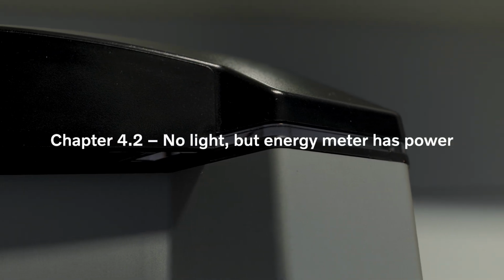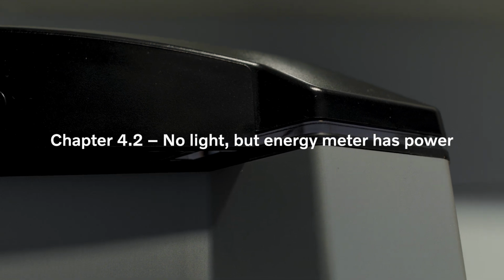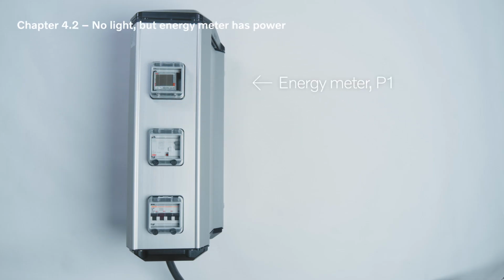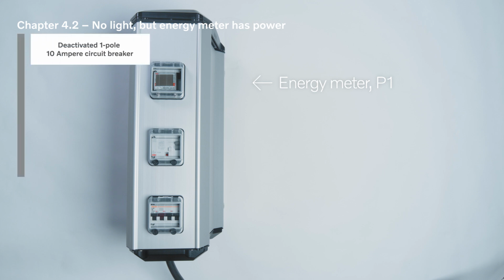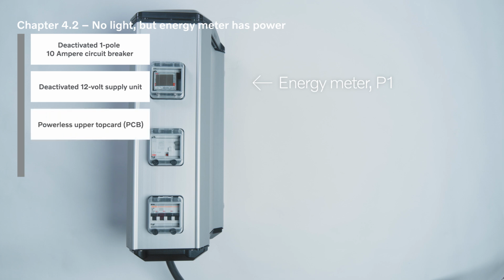If the LED indicator isn't displaying any light, but the left side energy meter, P1, has power, the power failure may be caused by one of the following issues: a deactivated 1-pole 10 ampere circuit breaker, a deactivated 12-volt supply unit, or that the upper top card PCB doesn't receive power from the 12-volt supply unit.